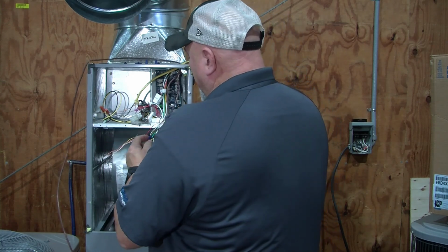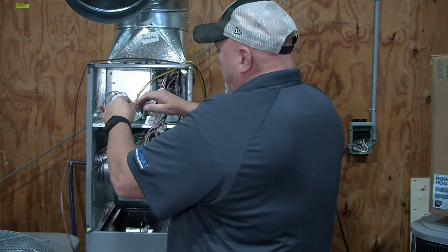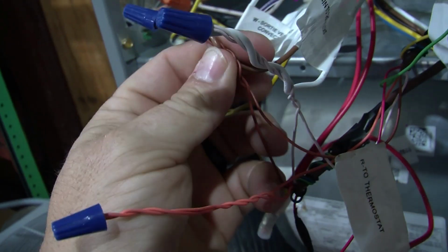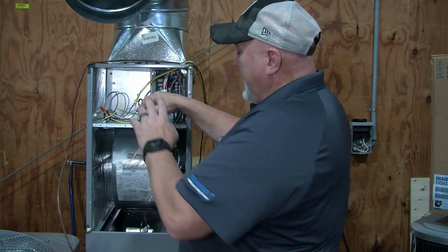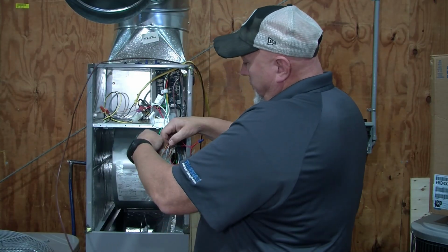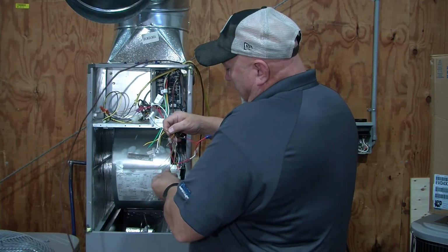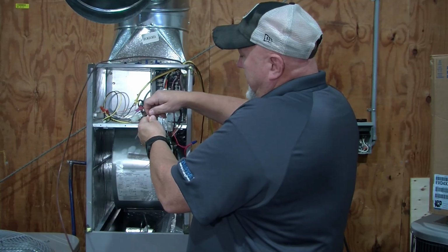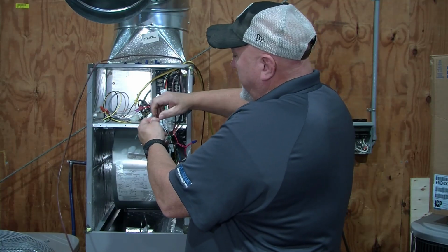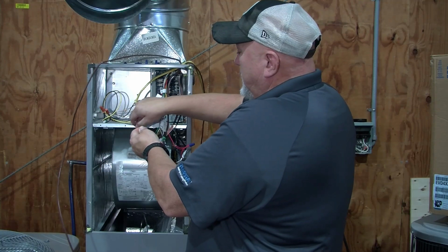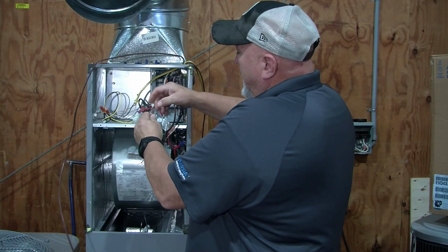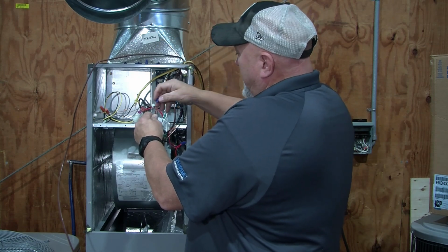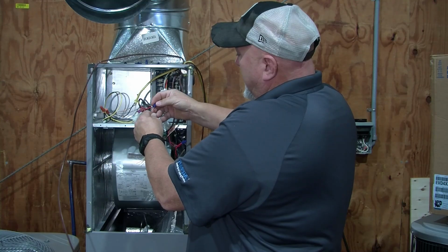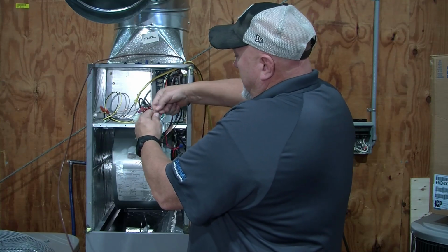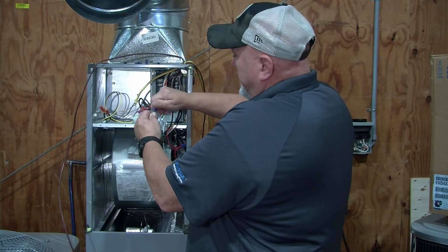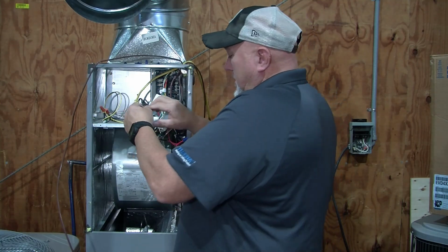Alright, and then next we're going to go with our common. And most people, the ICP on this one is using brown this year. So we got brown on the common, and so I'm going to use my brown on my thermostat wires. A lot of the people use the blue. You can use either one, as long as you know which one it is. You could use black if you wanted to, but we're just using brown for this video and this example. I usually use brown just because that's what they're using, and that way I can keep everything straight. Alright, so we got our red and we got our brown.